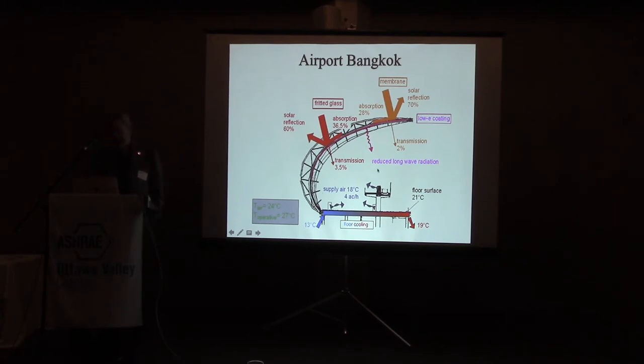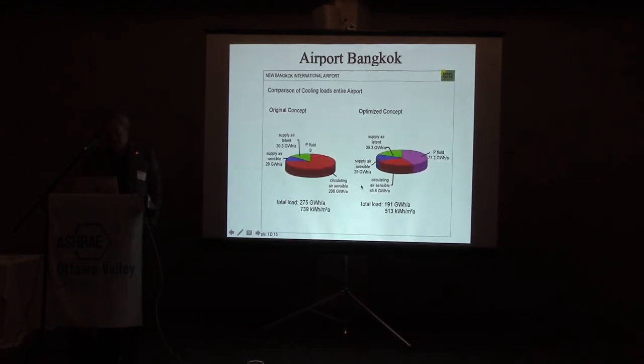So that was the idea of the construction. What the design engineers found was that if we were going to have, as usual, a full air system, the total load would be like 739 kilowatt hours per square meter a year. But by having a major part of the energy removed by a water-based system and by the floor cooling, they could reduce the energy use by about 30%.